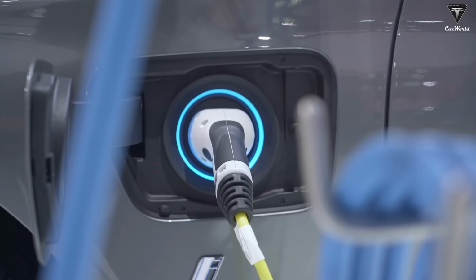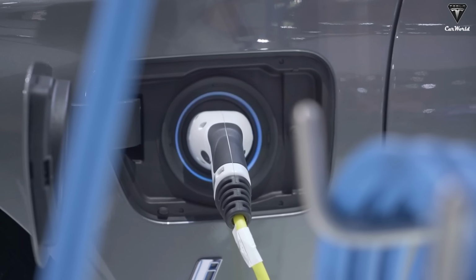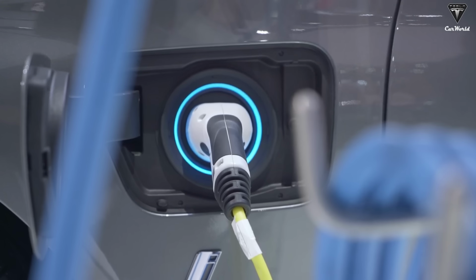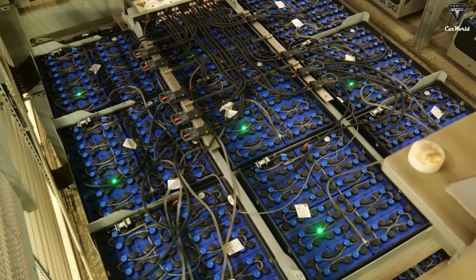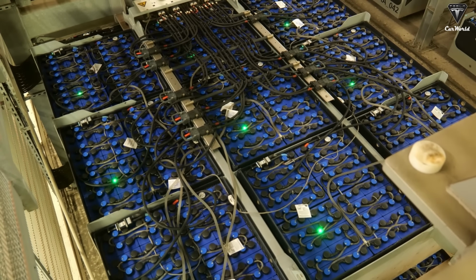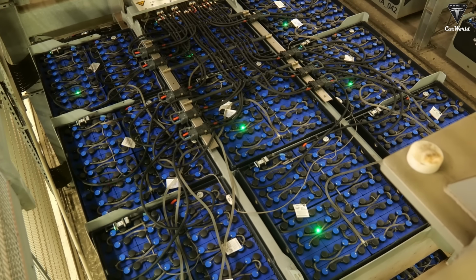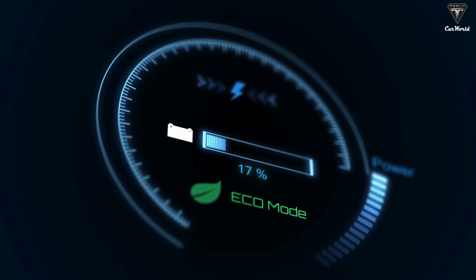This becomes especially important when you consider that not every cell inside a battery pack ages at exactly the same rate. Small differences in temperature, resistance, and charge level can cause individual cell groups to behave differently over time. The BMS constantly compares these measurements and can limit charging or power output when conditions become unfavorable.